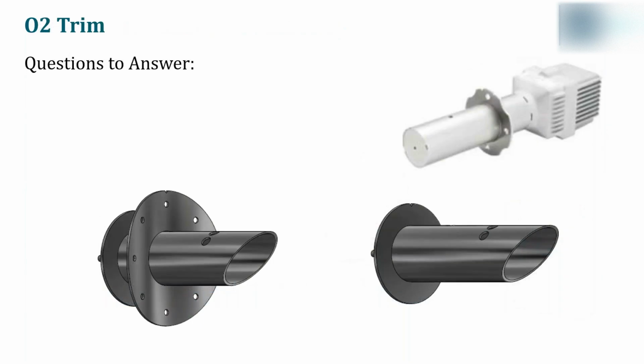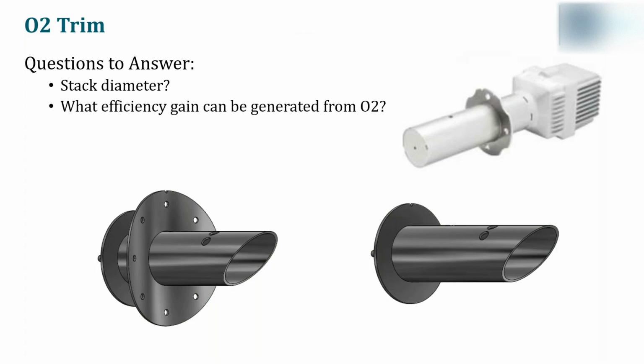Now, O2 trim. This one is rather simple. You need to know the stack diameter. You have to ask yourself, what efficiency gain can be generated from the O2? And this is something you have to consider. Where is the burner boiler currently running versus what is the potential where it could be running? And finally, what is the payback period?